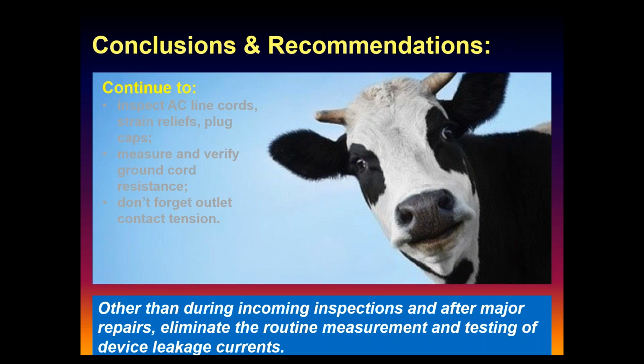So what's our takeaway from this, NFPA 99 versus manufacturers, like infusion pump manufacturers? They want you to perform safety tests, they want you to do leakage tests. Now, manufacturers still have to embrace this. Maybe they've gotten rid of the requirements for routine testing. They still have it in there that it's maybe an okay, reasonable thing to do when you first inspect the device, or if you're doing major repairs related to the inside of the device, check it again, but it doesn't need to be done periodically. Even if the manufacturer says you have to do it periodically, it's probably for this reason, or because it's something they want to sell in the name of safety to charge you more money.